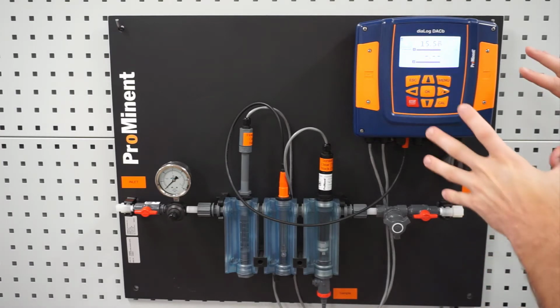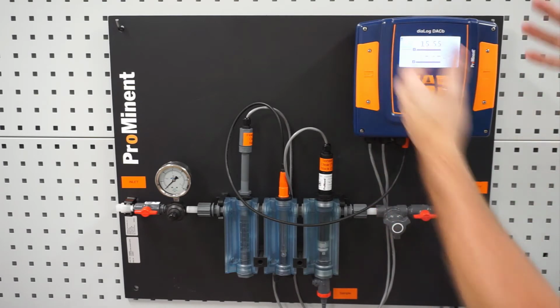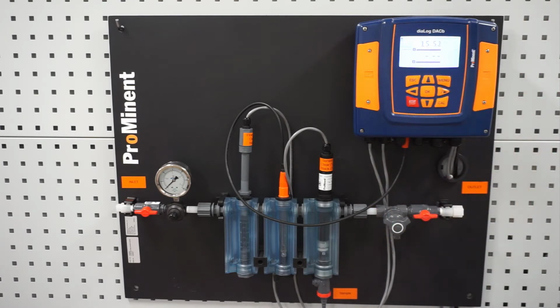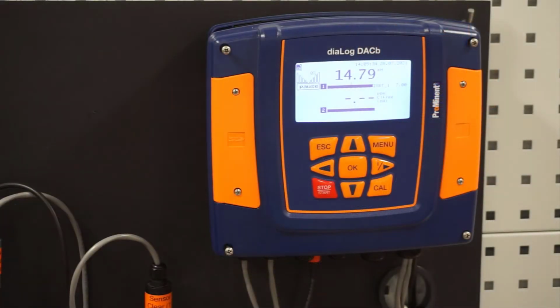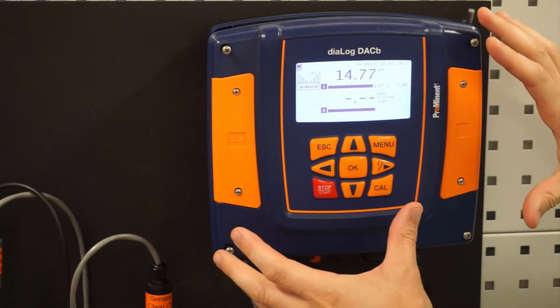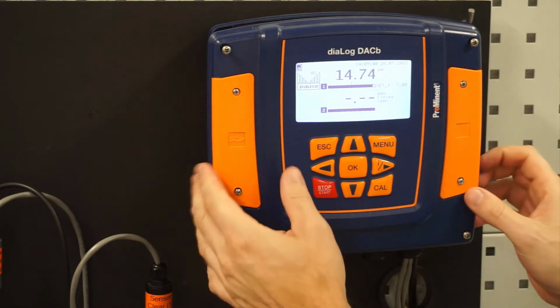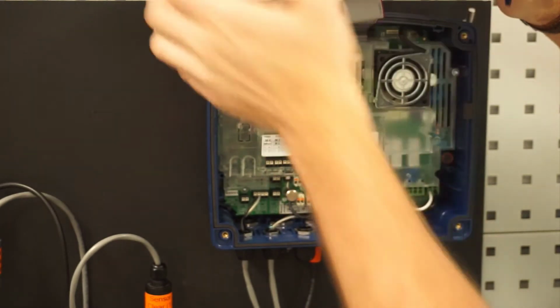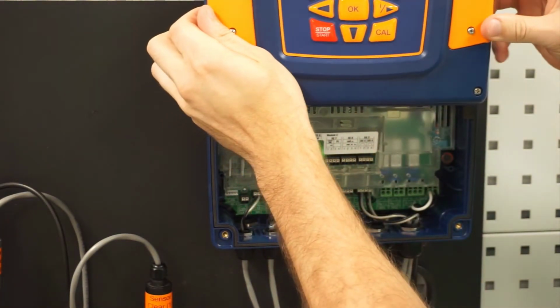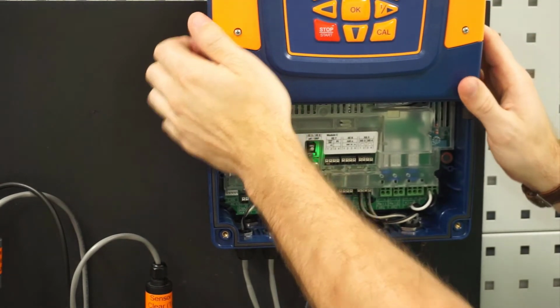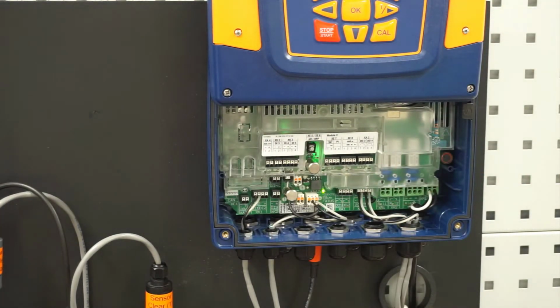Next, we're going to go into the controller, and I'm going to open the hood up and show you what some of the wiring looks like. We have our 4 screws loosened here, so now we're ready to remove the hood. On the hood, you'll see that there are 2 tabs on each side. That will allow us to park the hood here at the top so we don't have to hold on to it. It gives us easy access into the actual DACb here. All of our controllers, whether it's a DACb or an Aegis 2, they have those tabs so you don't have to just leave the hood of the controller just dangling down.